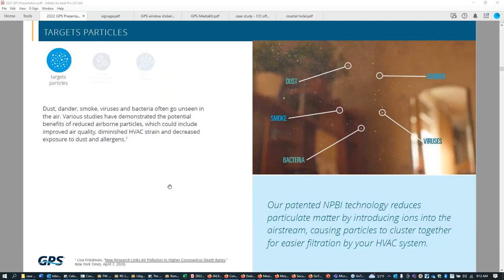So with particulate, what we're doing with the carbon fiber bundles is streaming positive and negative ions into the air. And as that happens, the dust, the smoke particles, the viruses, dander, all these things have the ability to be imparted with a positive or negative charge. And as that happens, and then the air mixes in the airstream, in the ductwork, and then out in space, the positive and the negatively charged particles can join together because positive and negative charges attract.